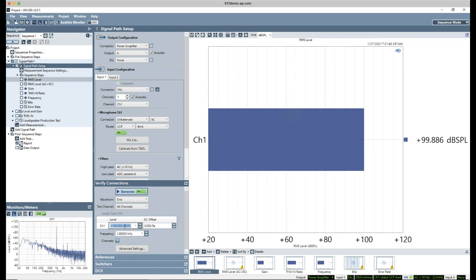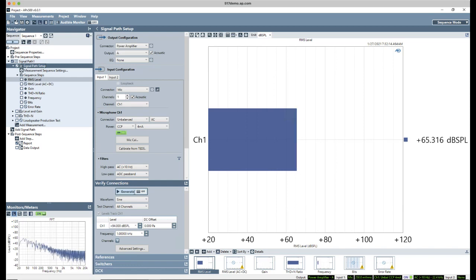I mean, here the speaker is quite good. We calibrated at 94 dBSPL. When I set the generator to 100 dBSPL, we're quite close. We're within 0.1 dB, so this is a pretty well-behaved speaker, but that is by no means guaranteed. So if I'm going to use 94 dBSPL as my test level, I calibrate the speaker to 94 dBSPL.